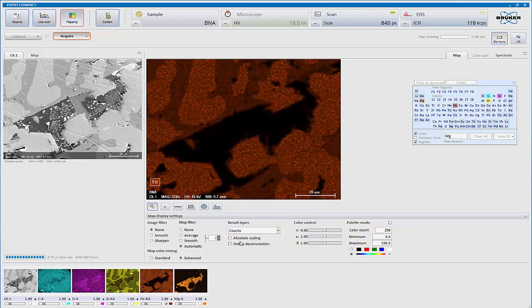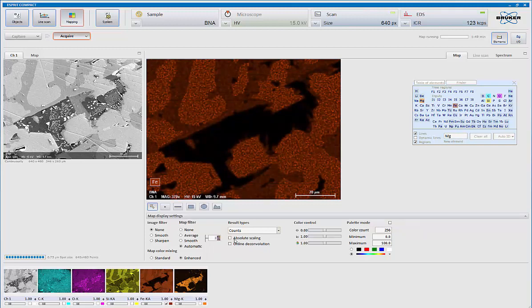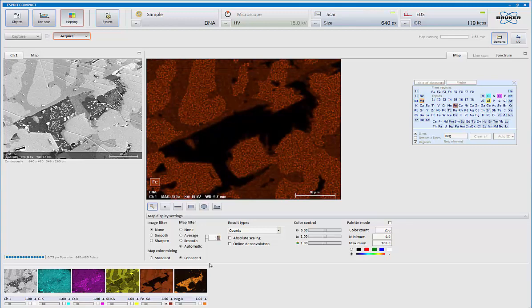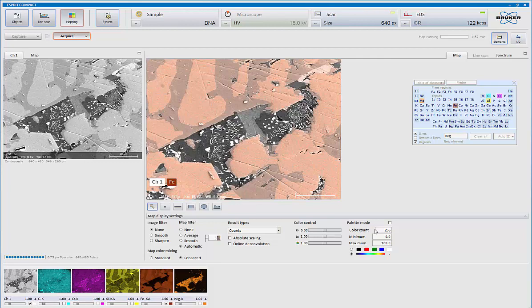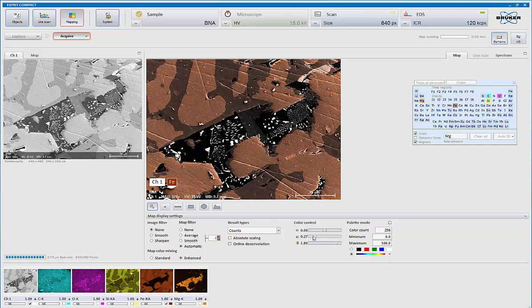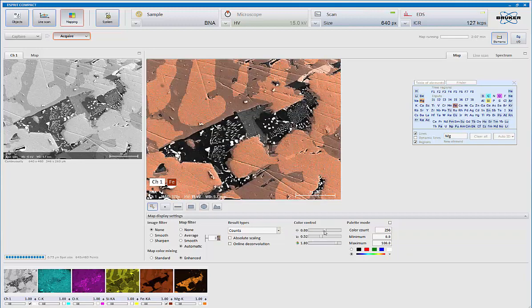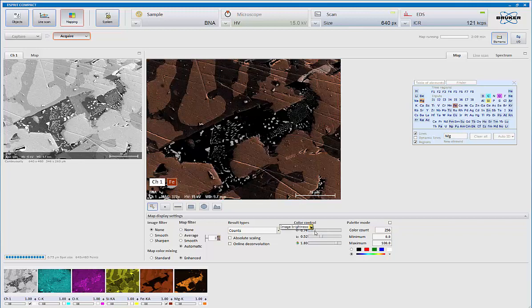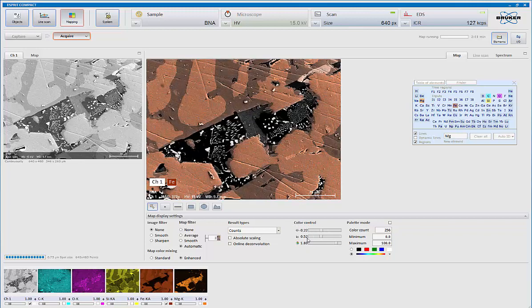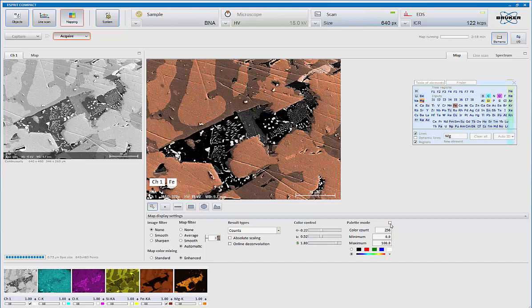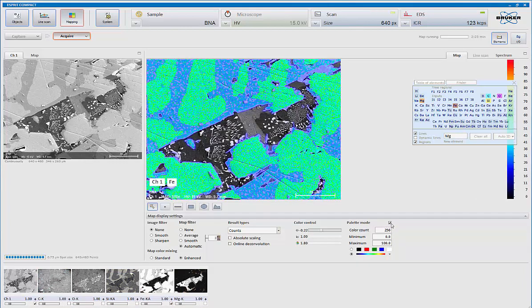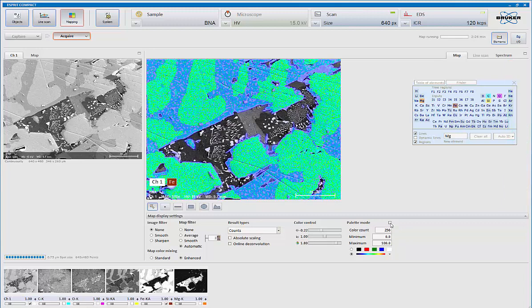You have the choice of displaying your maps in absolute or relative scaling, and there is built-in online deconvolution, so if we have an overlap in the system, the system will break the overlap apart and show us the two individual components. I can bring back the image, increase the saturation of the color, adjust brightness and contrast levels, adjust gamma within the system, and also remix pseudo-colorings if I wish, to show relative intensities based on color.